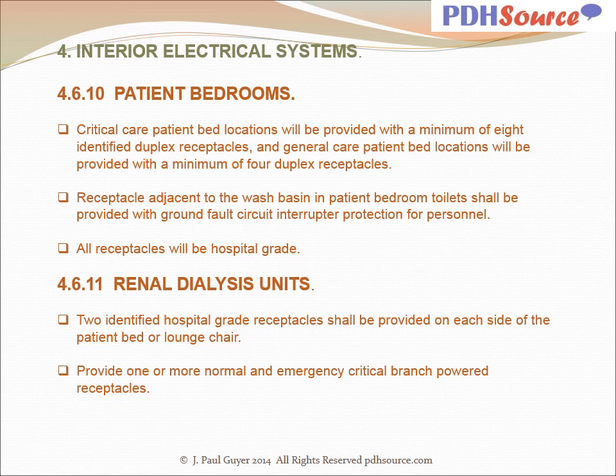Critical care patient bed locations will be provided with a minimum of 8 identified duplex receptacles, and general care patient bed locations will be provided with a minimum of 4 duplex receptacles. Receptacle adjacent to the wash basin in patient bedroom toilet shall be provided with ground fault current circuit interrupter (GFCI) protection for personnel. All receptacles will be hospital grade. In renal dialysis units, 2 identified hospital-grade receptacles shall be provided on each side of the patient bed or lounge chair. Provide 1 or more normal and emergency critical branch powered receptacle.